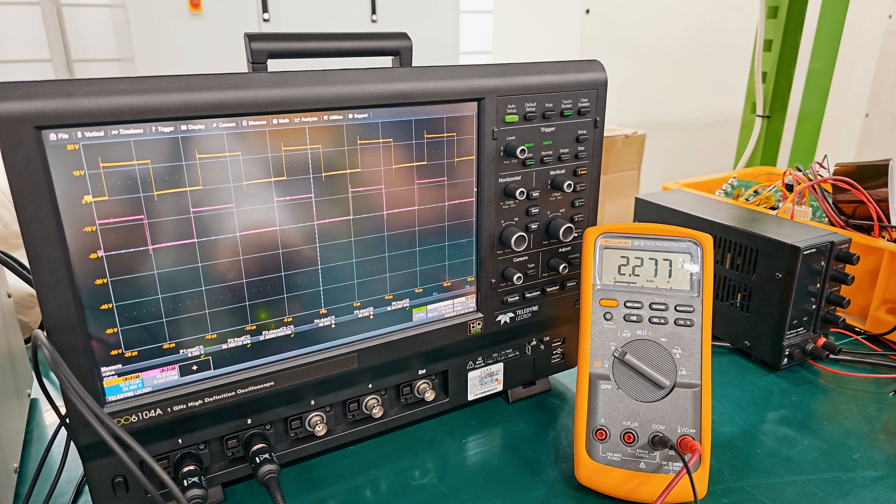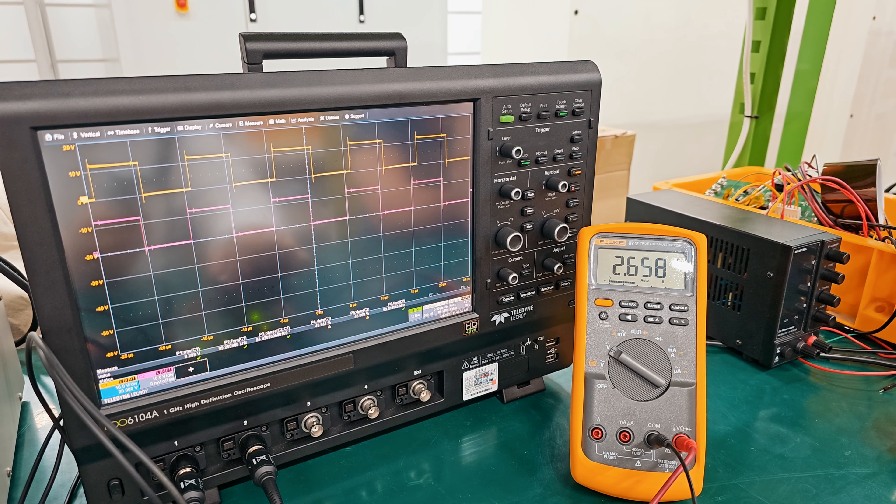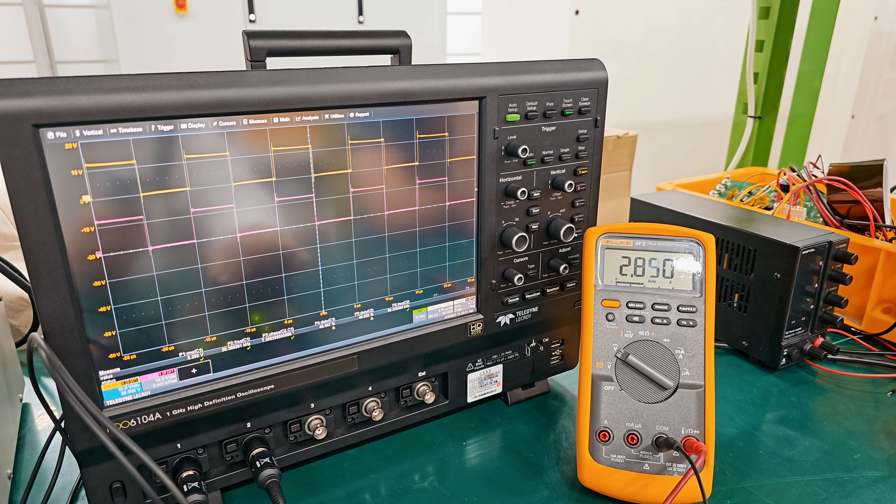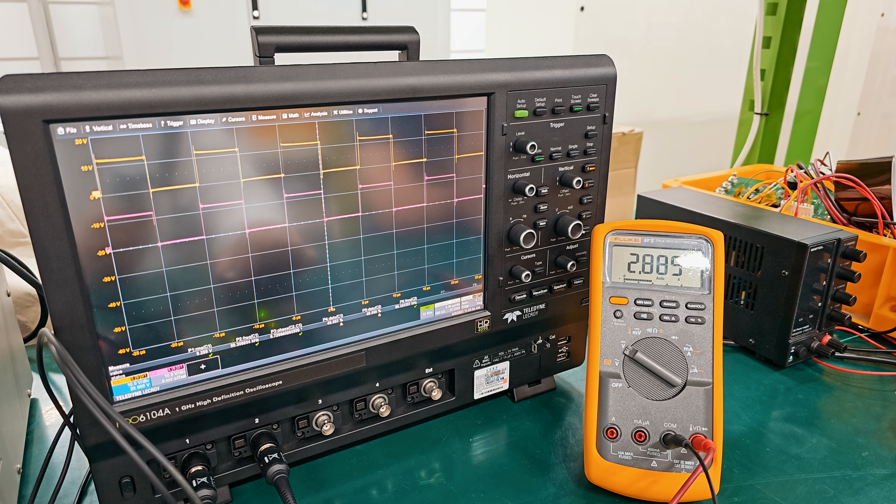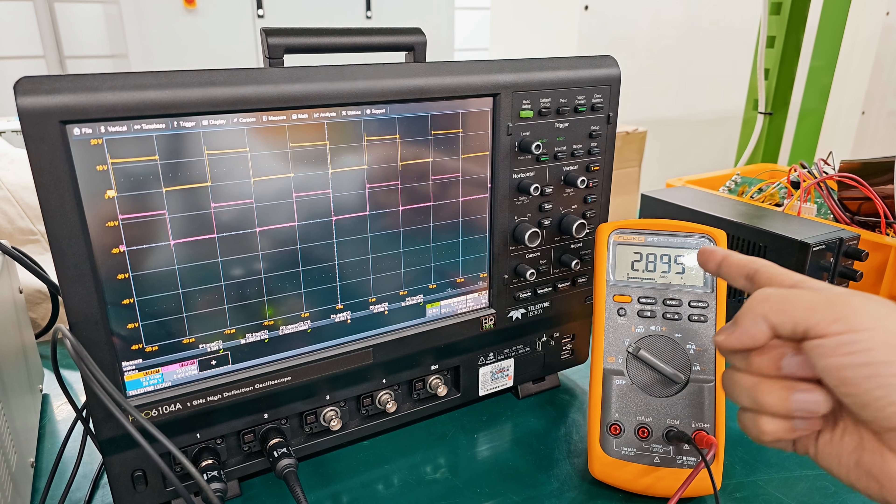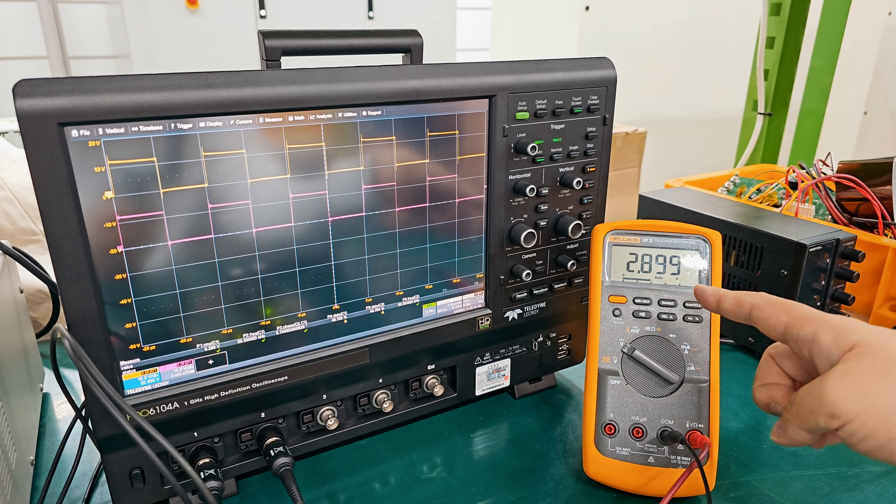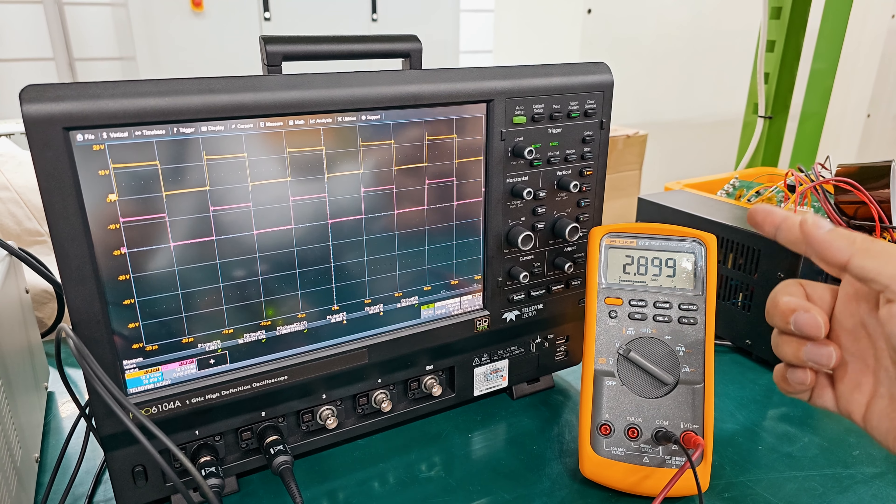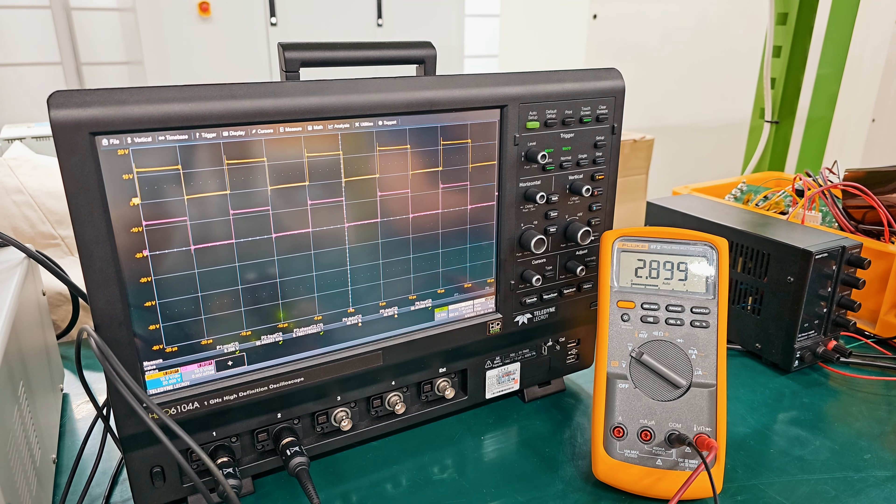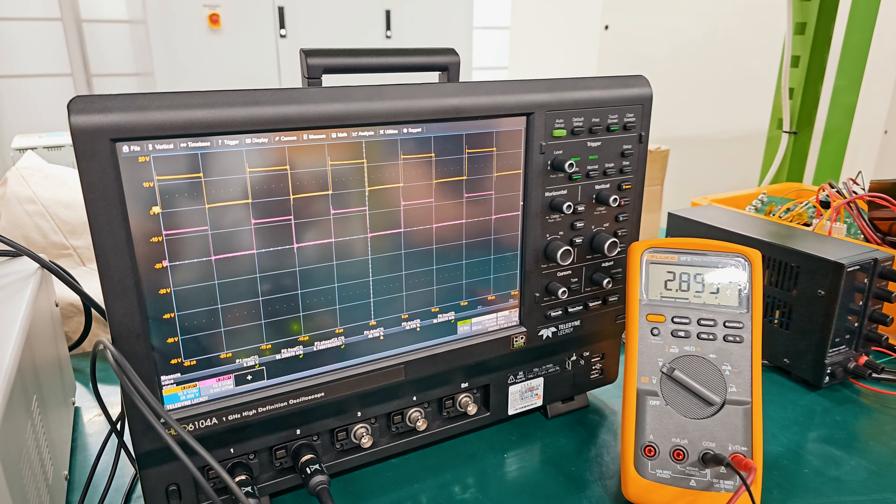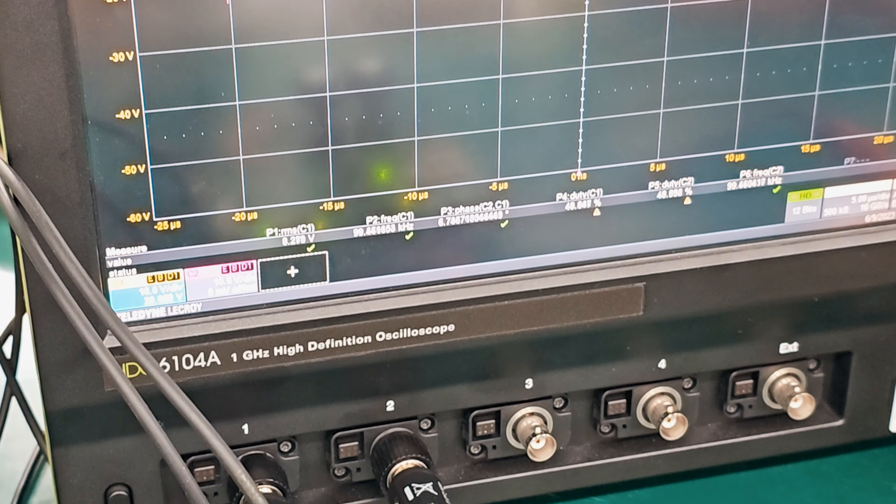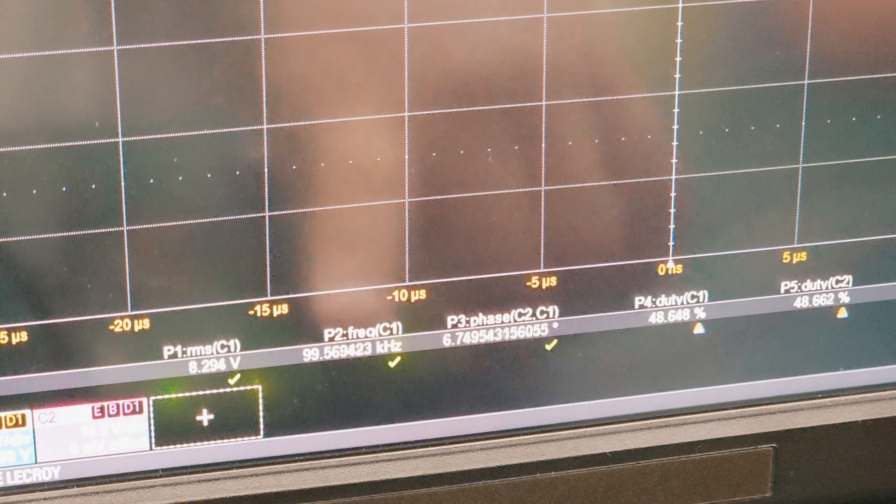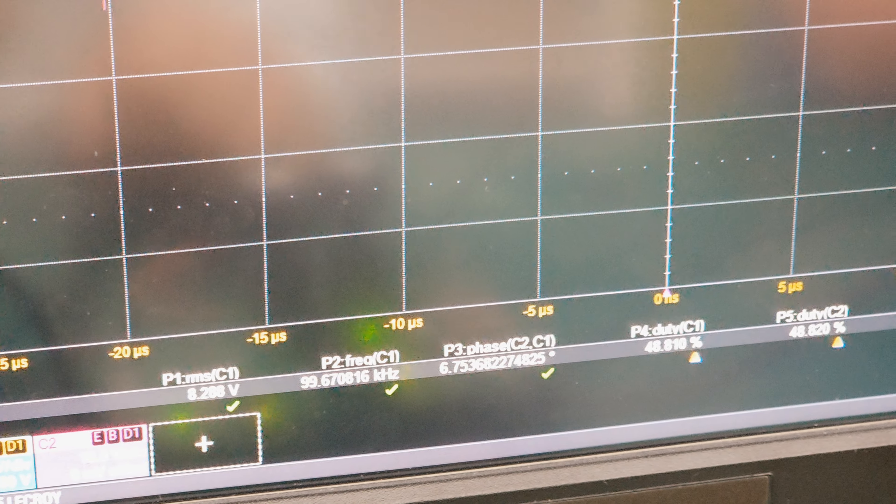Maximum voltage 2.8, maximum 2.9. If phase shift control voltage is over 2.8, PWM is fixed, phase shift minimum power control. Right now condition is phase shift control 2.67 is minimum value at 100 kHz.